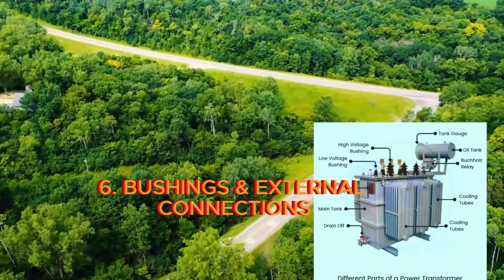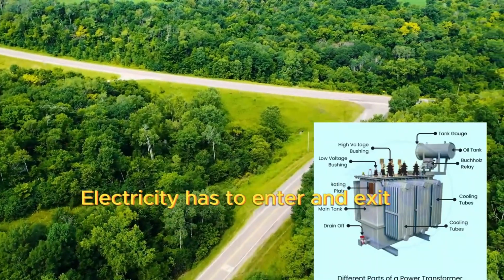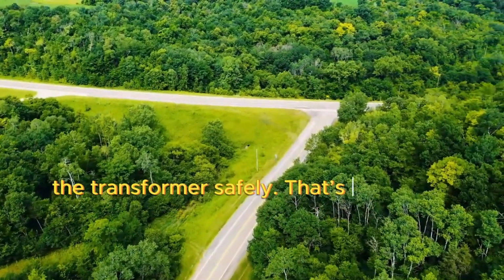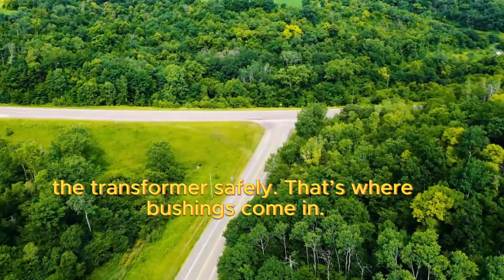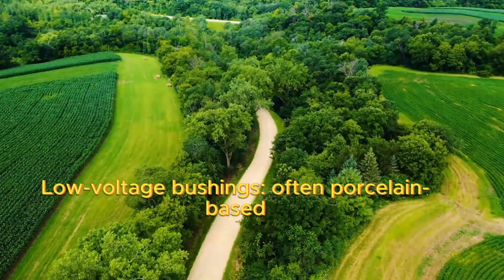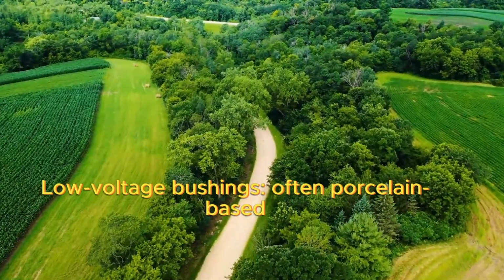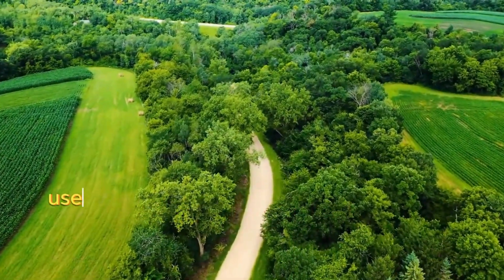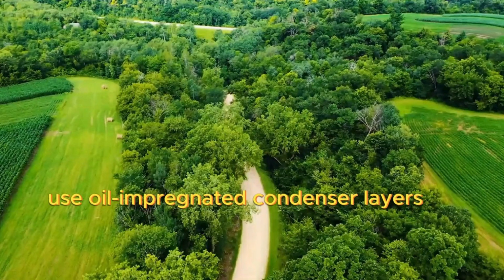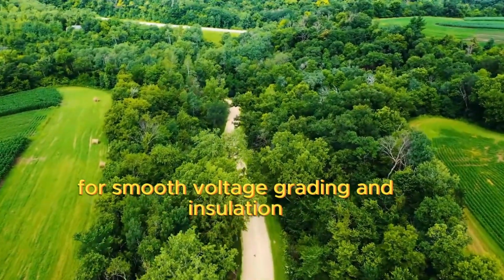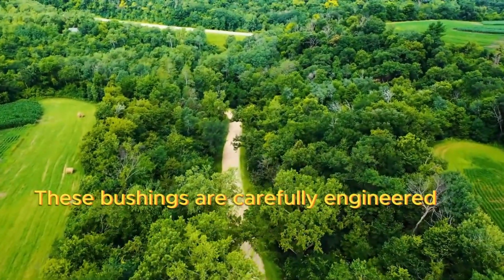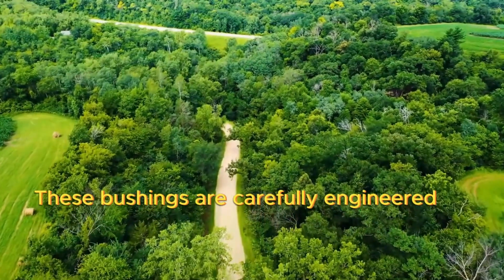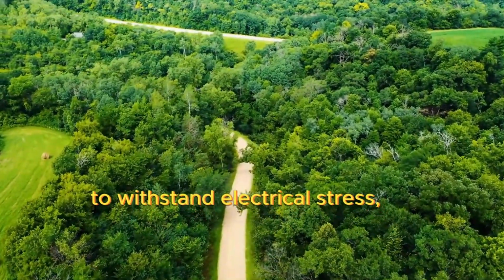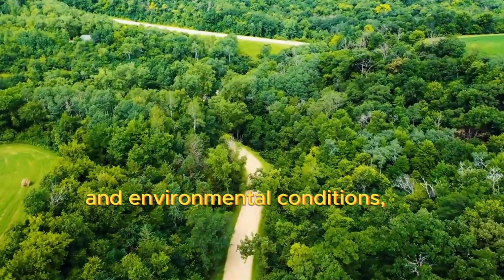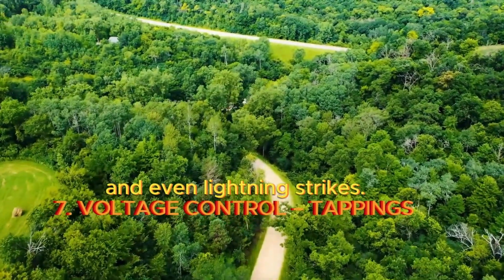Bushings and external connections. Electricity has to enter and exit the transformer safely. That is where bushings come in. There are two types. Low voltage bushings, often plain porcelain based. High voltage bushings use oil-impregnated condenser layers for smooth voltage grading and insulation. These bushings are carefully engineered to withstand electrical stress, environmental conditions, and even lightning strikes.